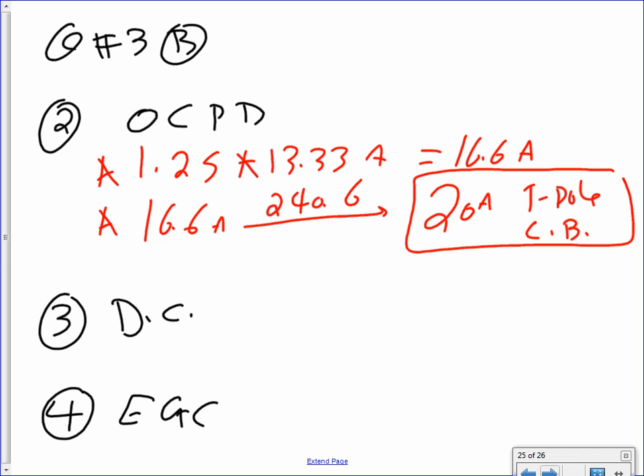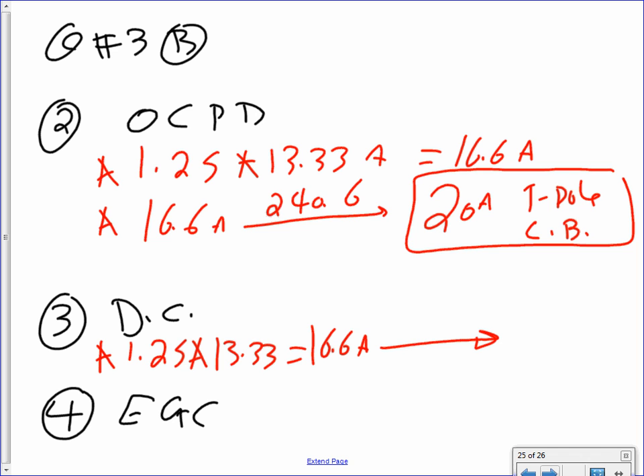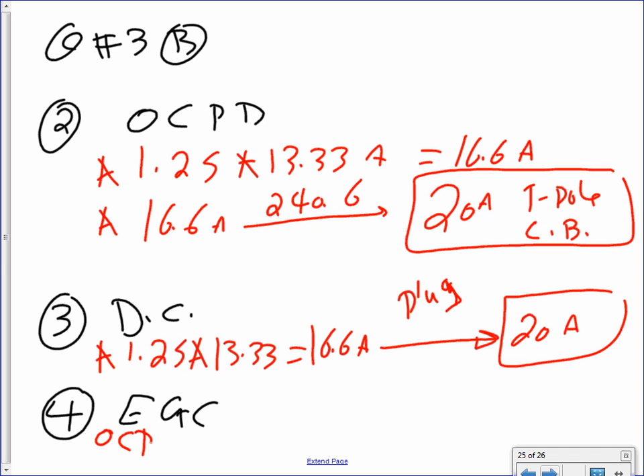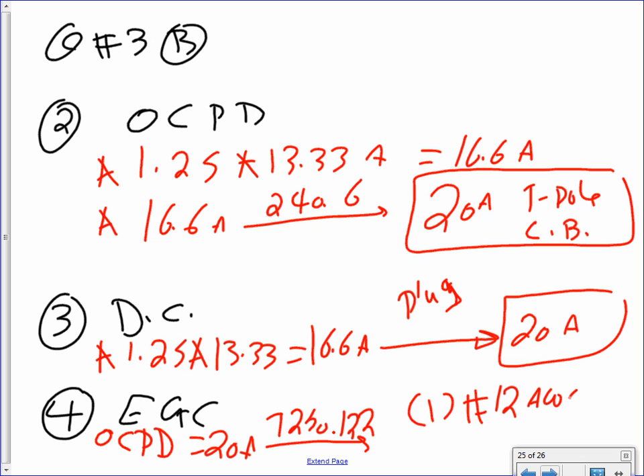Disconnect. For disconnect, guys, the same thing. 1.25 times 13.33, 16.6 amps. That will get you a 20 amp disconnect, and the type that we use is a plug. So we have a plug that's rated for 20 amps. The last thing is the equipment grounding conductor. You take the overcurrent protection device, which was 20 amps, take it to table 250.122, and that will get you one conductor, number 12 AWG, in an NM cable.